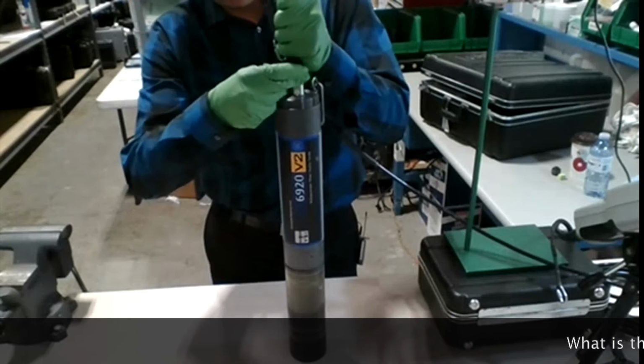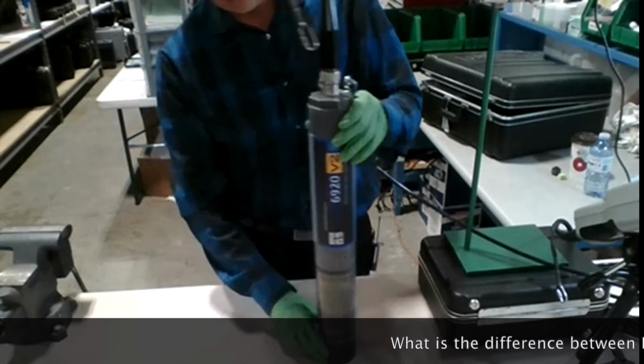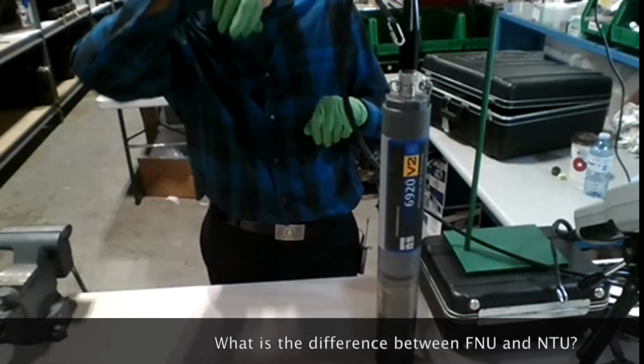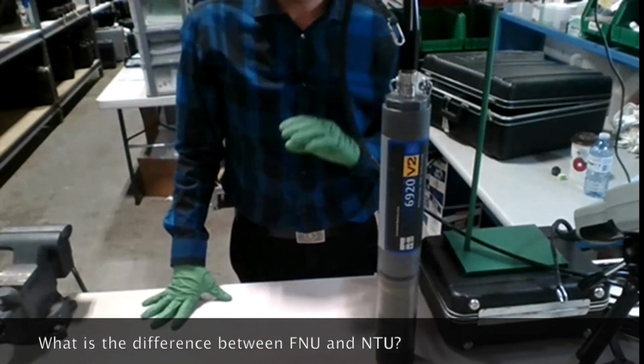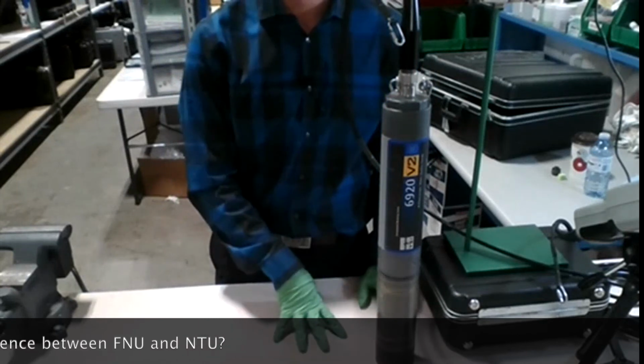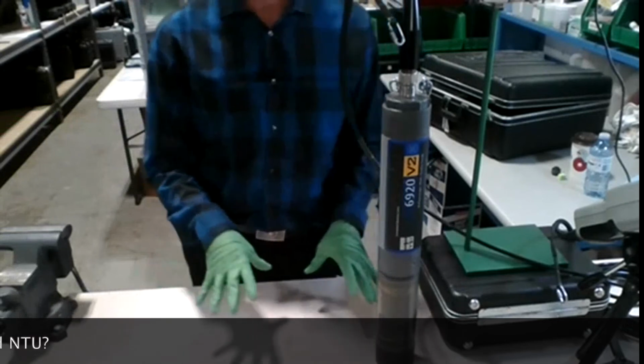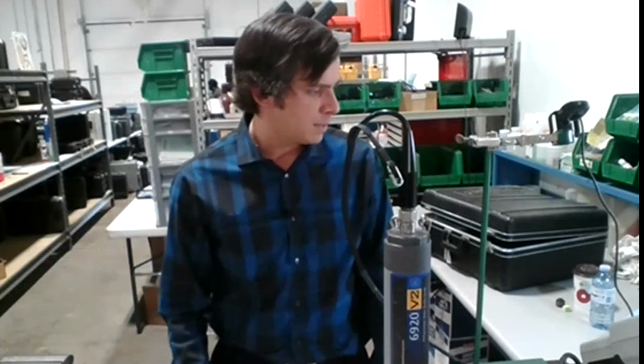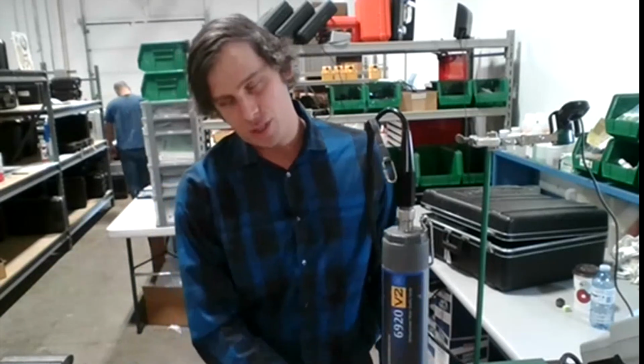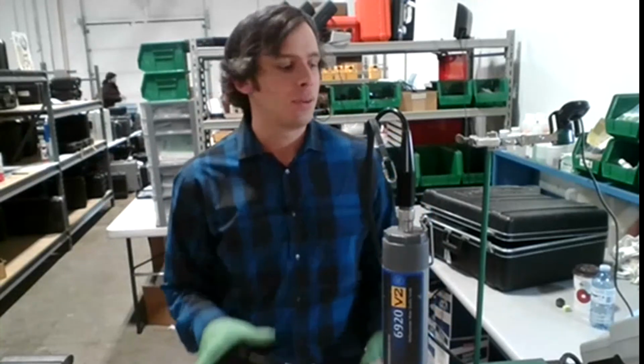So actually this is more of a comprehension question, because the 6920 doesn't actually measure FNU. So I'll explain the difference between NTU and FNU. FNU is actually more of a European term, but I have gotten technical calls because somebody was going through the turbidity settings on a YSI Pro DSS. And because YSI is becoming more international and prevalent, they have to offer different turbidity units that meet European standards. And I guess the other more in-depth difference is that NTU uses white light to measure turbidity, where FNU uses a near infrared light to measure turbidity. But the readings are the same, just how they're measured and given is a little bit different, but the readings are relatively the same.